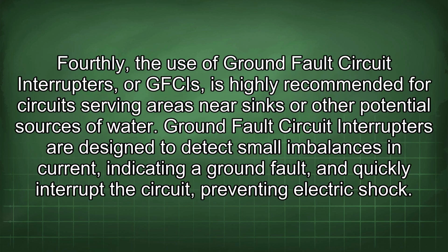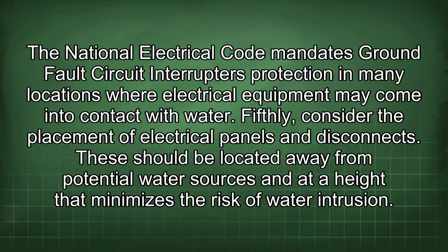Fourthly, the use of ground fault circuit interrupters, or GFCIs, is highly recommended for circuits serving areas near sinks or other potential sources of water. Ground fault circuit interrupters are designed to detect small imbalances in current, indicating a ground fault, and quickly interrupt the circuit, preventing electric shock. The National Electrical Code mandates ground fault circuit interrupter protection in many locations where electrical equipment may come into contact with water.